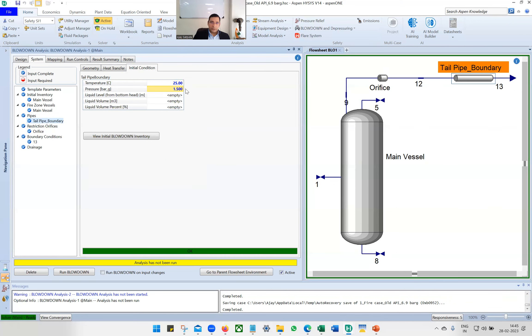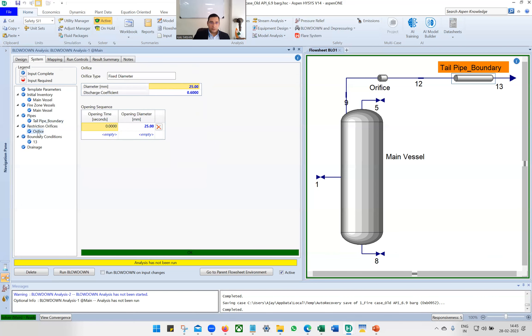The pressure here is the superimposed back pressure — the maximum pressure in the flare header. Assume it is 1.5 bar gauge. For the orifice, the tailpipe is 4-inch (100 mm) and the restriction orifice size is 25 mm with a discharge coefficient of 0.6.